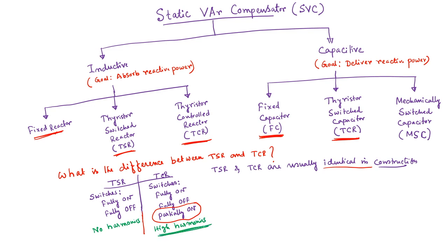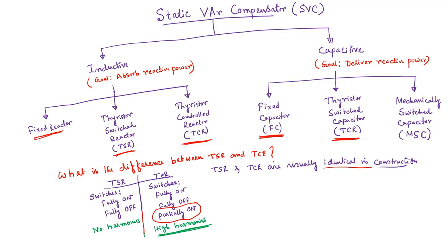And this high content of harmonics is one of the major limitations of the operation of TCR, which I already discussed in the last two lectures. Okay. And there should be some mitigation approaches as well for these higher order harmonics, like third harmonic, fifth harmonic, seventh harmonic and so on. Okay.